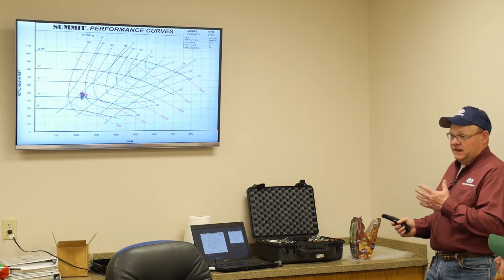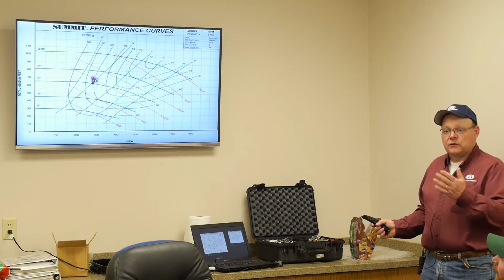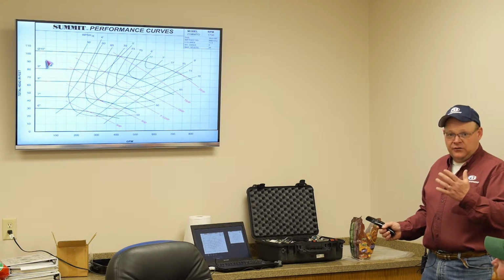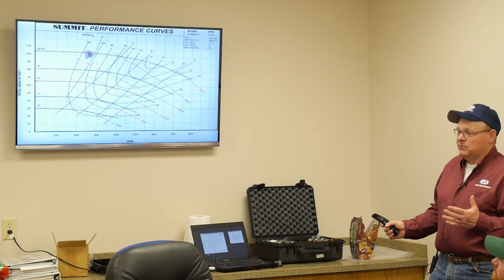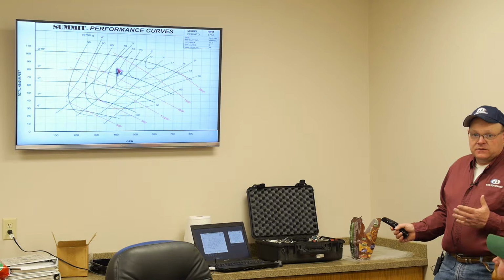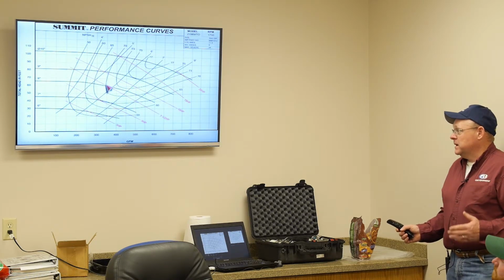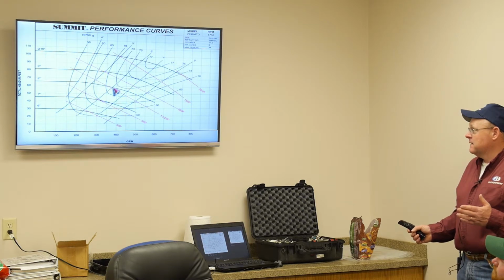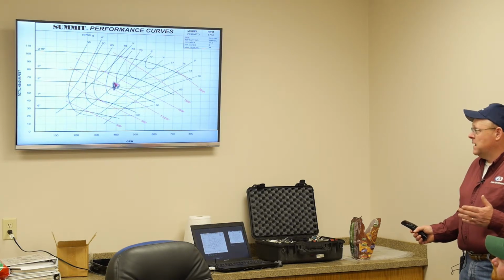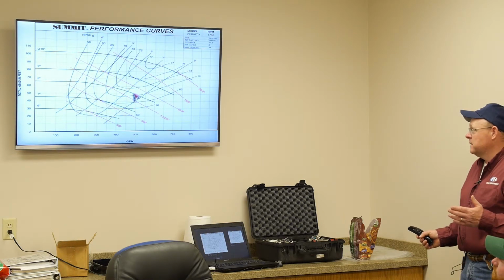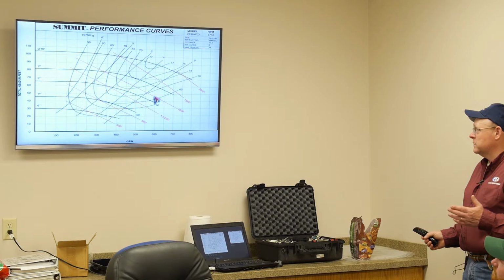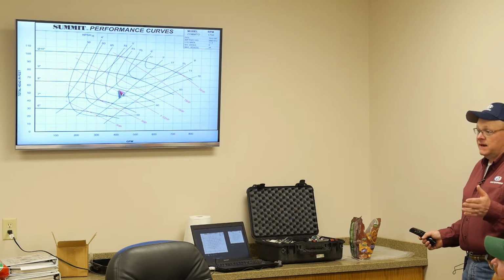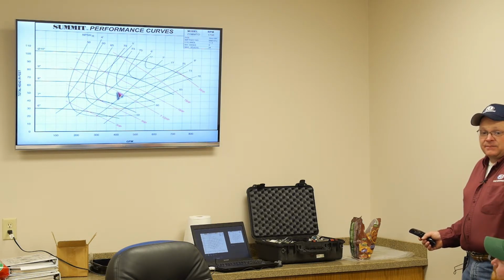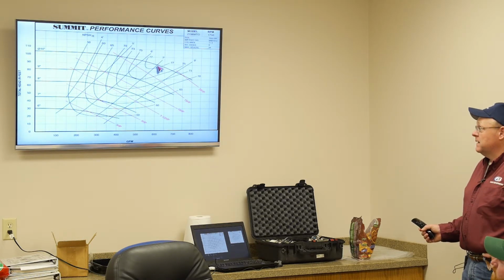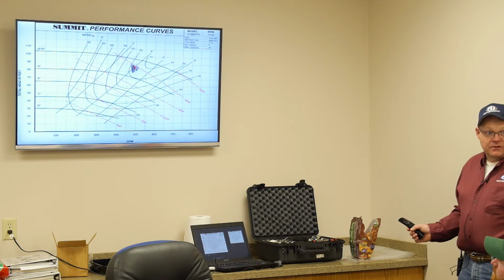So on all these curves, you'll see a lot of us, when we quote this, we'll put NOL, non-overloading power. We're going to put enough horsepower into it that it will run at any point on this curve without tripping out. The problem with that is, say I spec'd a pump to operate right here. My non-overloading power would be 10 horsepower on this curve, right? I got an 8-inch impeller, my non-overloading horsepower would be right here. Plant changes, management, we want more performance out of that pump. All they got to do is go back, pull the volute, put a 10-inch impeller in it. Oh no, we're in trouble, we ain't got enough horsepower.